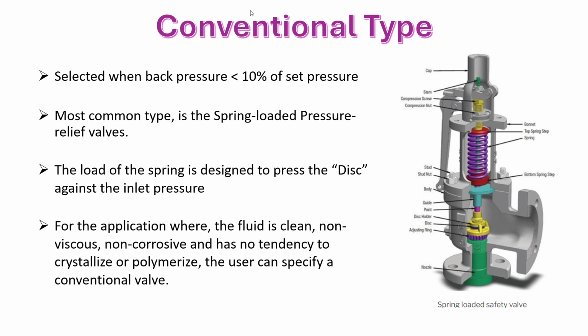Regarding limitations in steam service for conventional valves: while versatile, conventional PSVs are not ideal for steam service, steam boilers or superheaters. The main reason is the temperature sensitivity of the spring. The spring can contract or expand with changes in temperature, and the spring must be cooled to maintain its characteristics and stability against the set pressure.